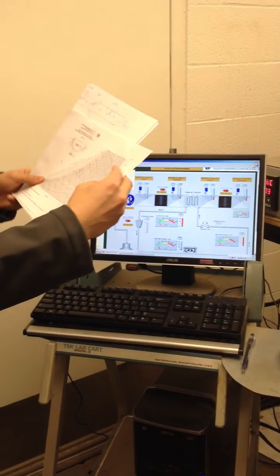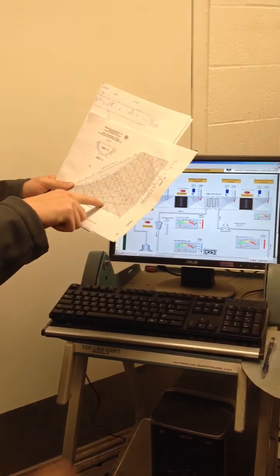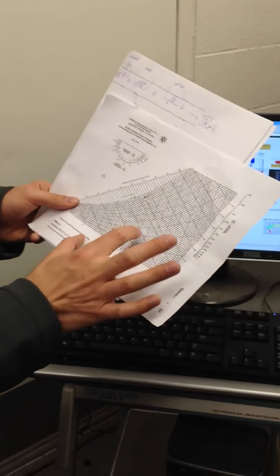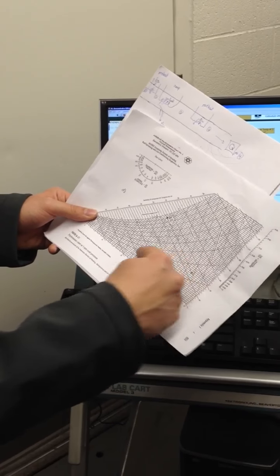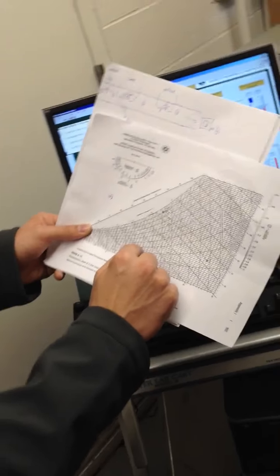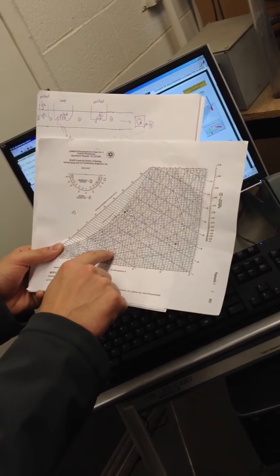That's humidity ratio, where's relative percentage? Oh, there you go, relative humidity. So say, for example, if it was 20 degrees and 25 relative humidity, 25 is right in between 20 and 30, right? Right, this way. So you just follow right about there. And then from here, you can get all your pieces of data.